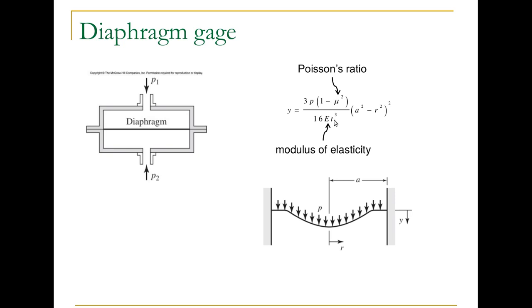So the thickness is in the denominator and you can see that the maximum displacement is going to be when R is equal to zero, that is whenever you're looking at the center of the diaphragm. The output of these sensors is usually linear with pressure as long as the deflection remains less than about one-third of the thickness of the diaphragm.